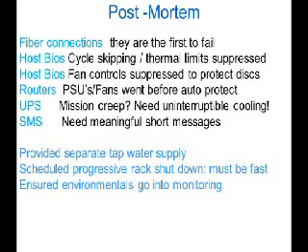The post-mortem was interesting, and it's a word of warning to you guys as well. The very first thing to fail was the fiber links — they go at about 40 to 45 degrees ambient. Therefore if you've got yourself mission-critical links, you better have a copper backup someplace.